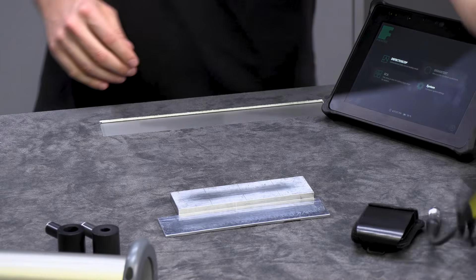Okay. So I connect a sigma test probe. It's really a standard probe of our common sigma test 2070 with the correct adapter cable. And now you saw the sigma test app gets active because the instrument recognized, okay, this probe was connected now. We go into sigma test, and we can now go to adjustment, and there we already prepared the values which are written on the standard. And if you'd like to change these values because you have a different standard, you can swipe right or left. Right swipe is to delete the value, or left swipe is to edit the value.